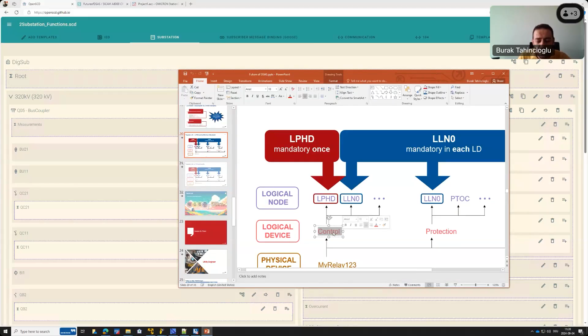So why do we have a root function? We must have a logical node — even though the others are optional, we must have something, and that's the LPHD, the physical device logical node. As we have an IED, which is a physical device, even if virtual, we need this LPHD. It's my choice to put the LPHD logical node under the root logical device. Maybe some vendors use other logical device names, but this is my choice to make it under the root logical device, root function.